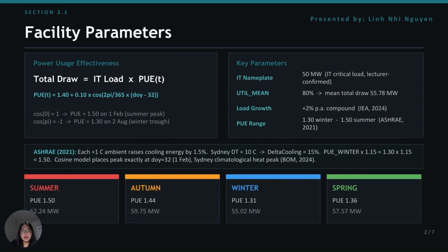The 50 megawatt is IT critical load only, so total draw is higher once cooling overhead is added, captured by PUE. The model has PUE as a cosine function, 1.5 in the summer and 1.3 in the winter, with a 10 degree seasonal swing and a 15% extra cooling load. Mean utilization is 80%, growing at 2% per year, giving summer highs at 62 megawatts and winter lows at 55 megawatts.